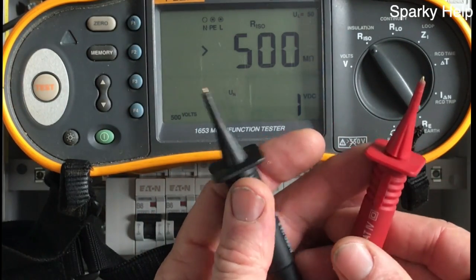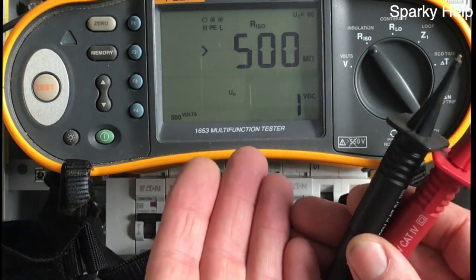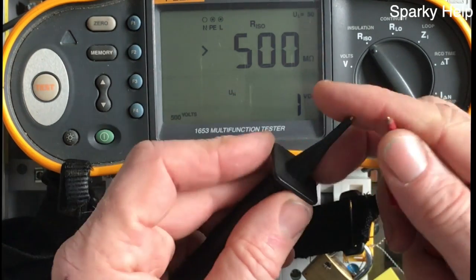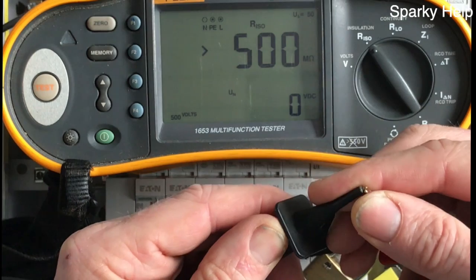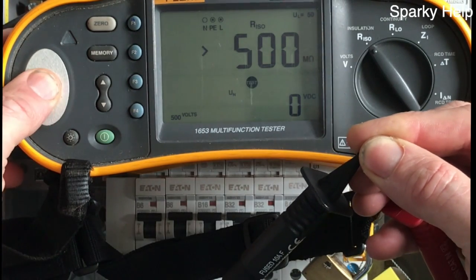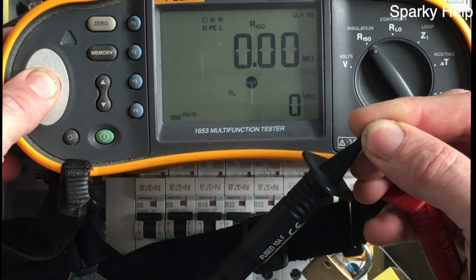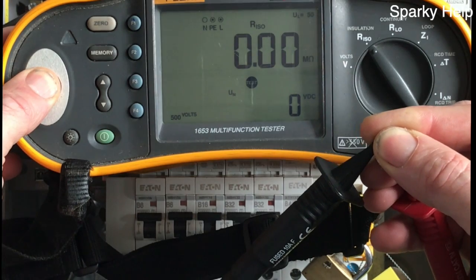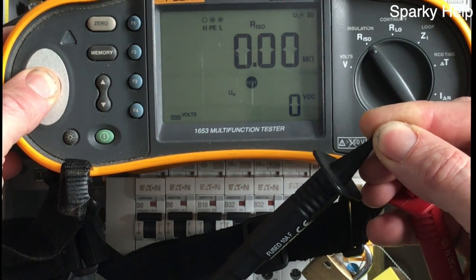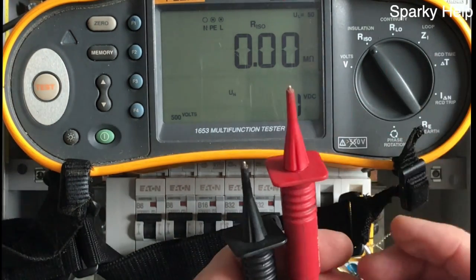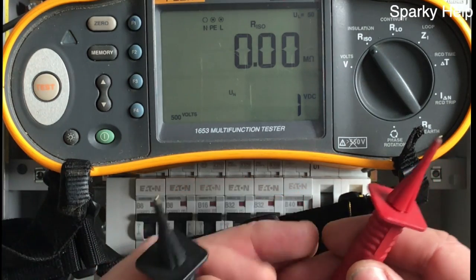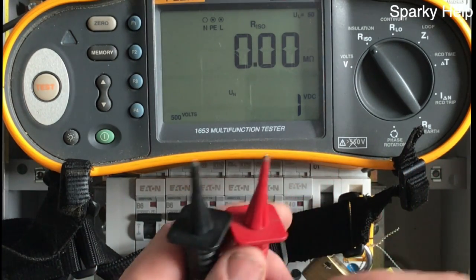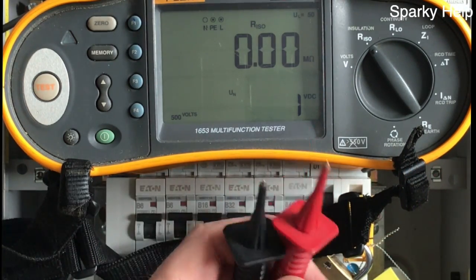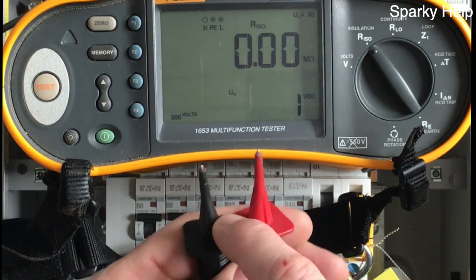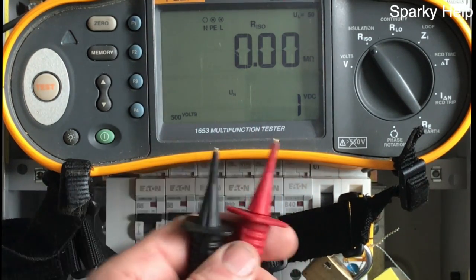So that's what an open circuit would look like, and that's a good value, it's obviously what we're after, just to make sure without electrocuting yourself. Okay, so that's fine, put that together. This is a dead short, and a dead short now reads 0.0 mega ohms. So we now know what the two extremes of the meter do. There's no need to zero it. People bizarrely sometimes say they need to zero the leads. No, you don't. Anyone who knows their stuff would know that anyway. So dead short, open circuit, meter works.